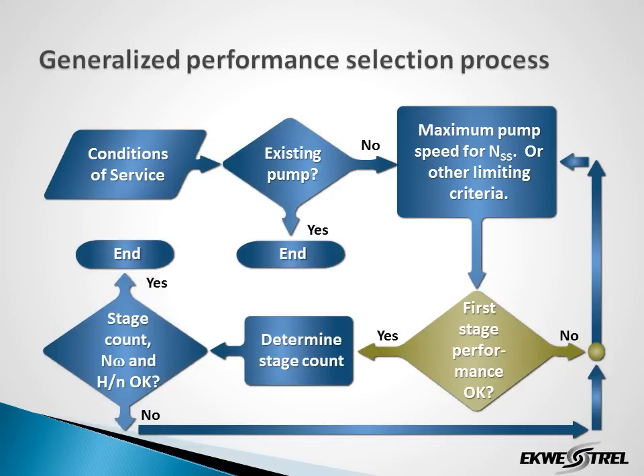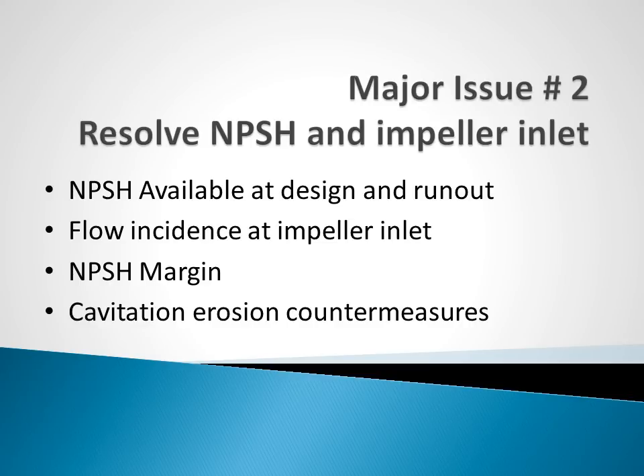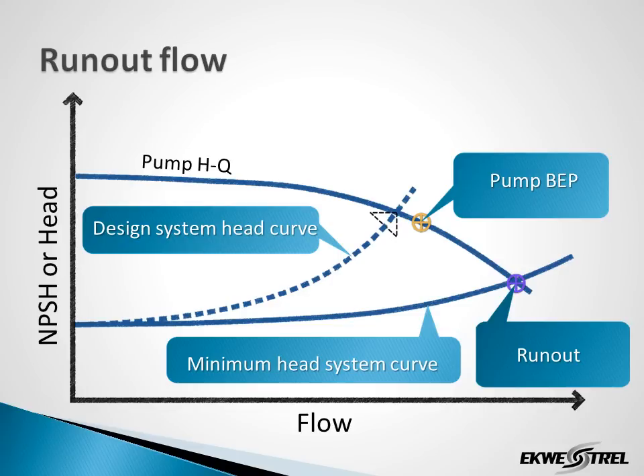We've talked about how the system curve affects the sizing of the pump, but suction performance of the first stage is a very important issue. Major issue number two: resolution of NPSH and the impeller inlet. This is actually a package of related issues including NPSH available, flow incidence, NPSH margin, and cavitation. Taking a look at the pump and system curves, there's usually a so-called run-out condition based on variations in the system characteristic. We have the design head curve here and a minimum head system curve, and the intersection of that with the pump curve is the run-out condition.